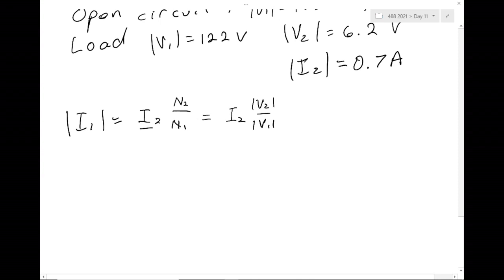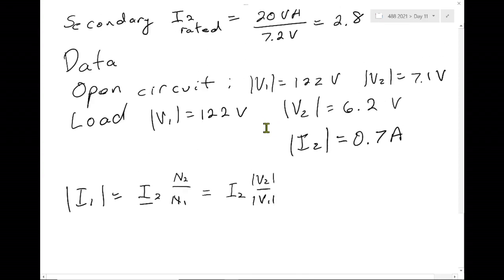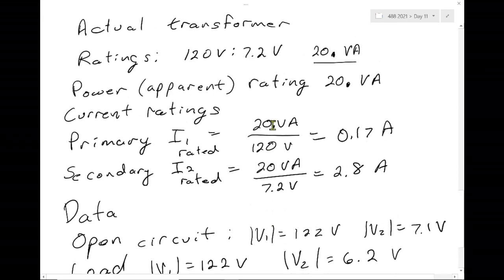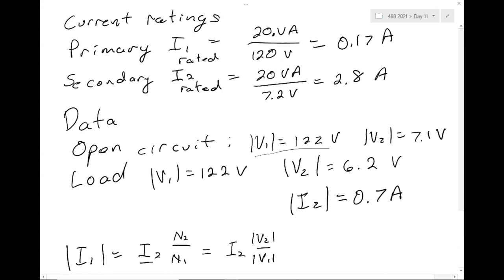Now, which V2, V1 do I use? I have three choices. I have the rating, so I can use 120 volts, 7.2 volts. I have open circuit values. I have V1, V2 open circuit, and then I have values when the transformer's loaded. Which ones do I use? There's no absolutely correct answer on this. You do not use the loaded values because we're going to come up with a different way to calculate those loaded values. But we use either the rated values or the open circuit. If I haven't done an open circuit test on the transformer, I don't have those, and I use the ratings. If I have done an open circuit test on the transformer, that's what I use because I think it's going to be more accurate than using the ratings.